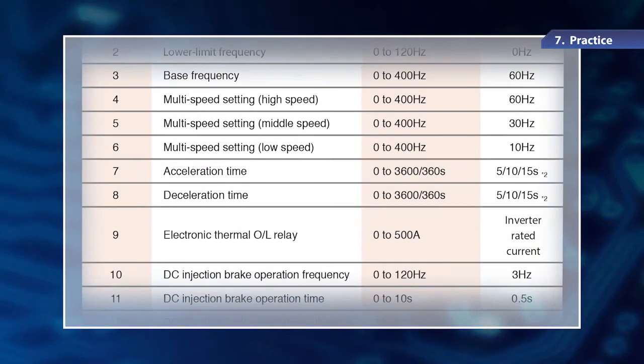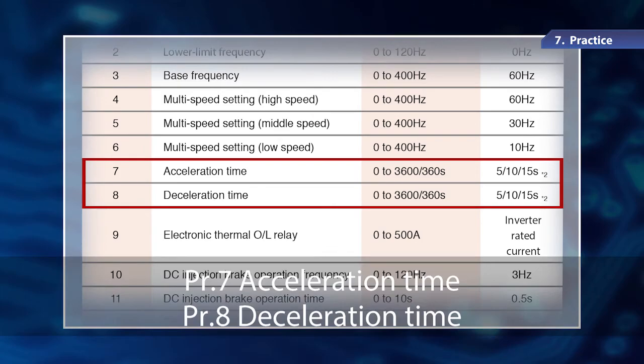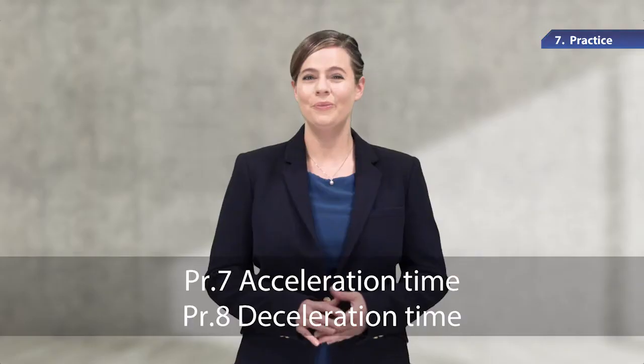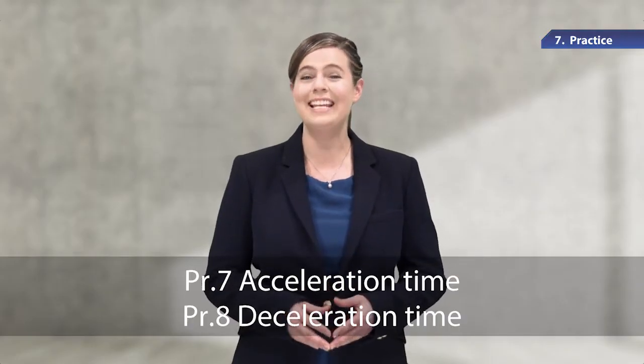As a useful inverter function, I'd like to show you the parameters to set the acceleration time and deceleration time to start or stop the motor. Parameter 7 is for acceleration time, and parameter 8 is for deceleration time. We are going to use these settings and the belt conveyor introduced in Chapter 1 as an example.